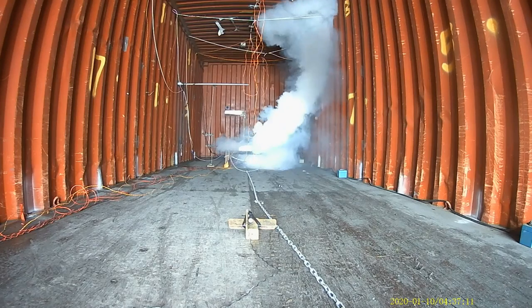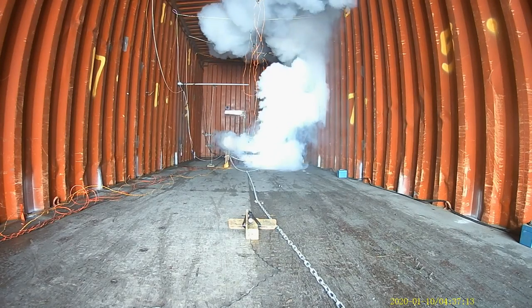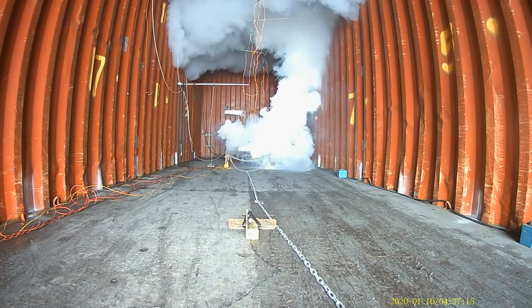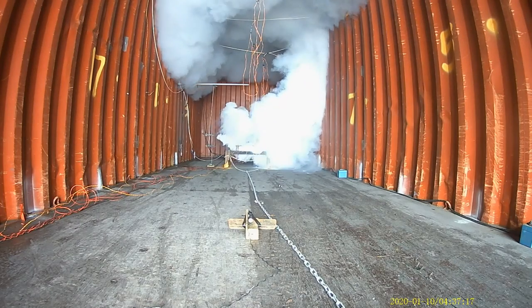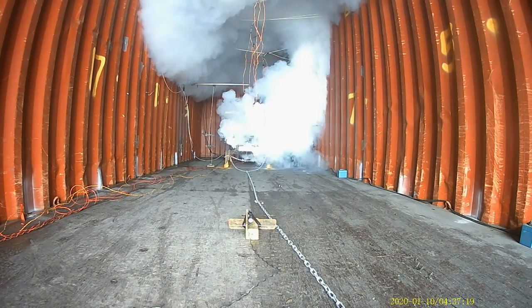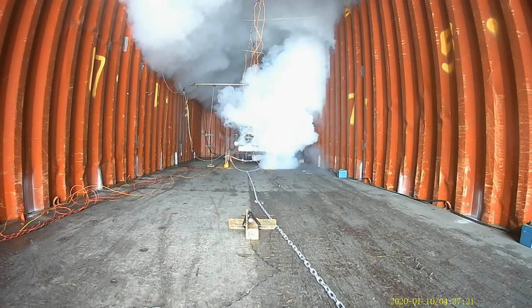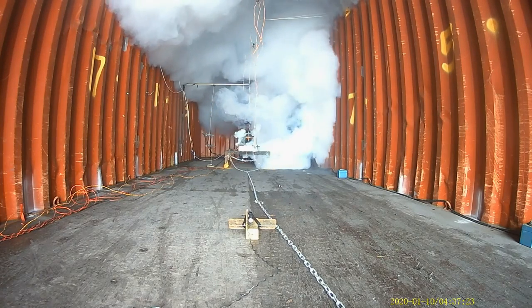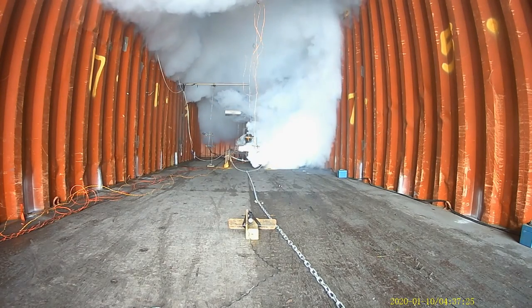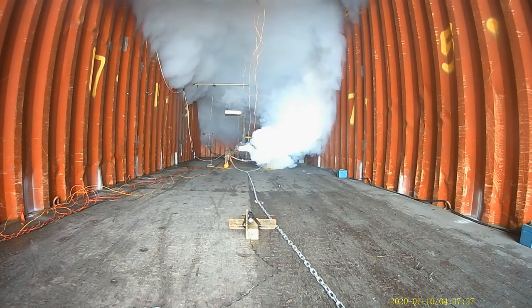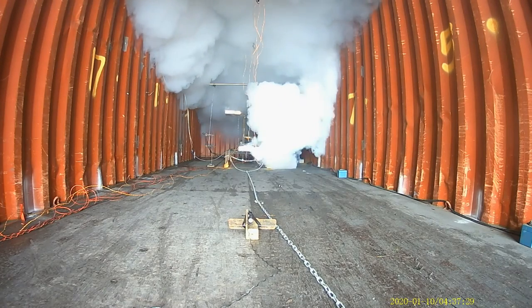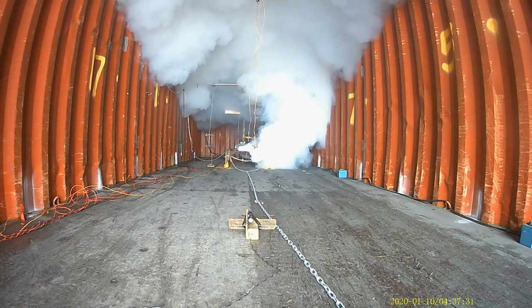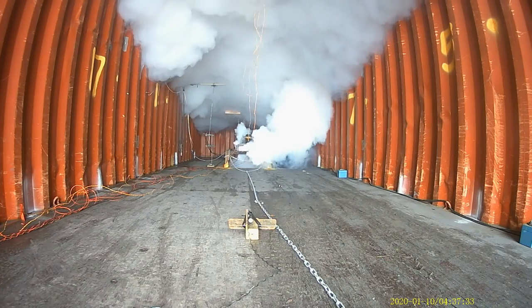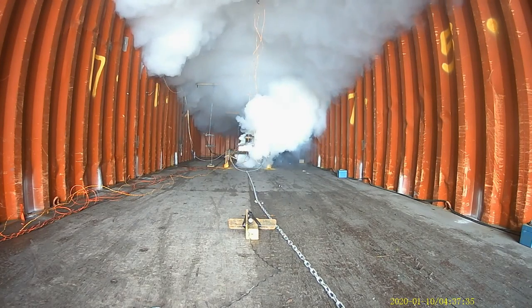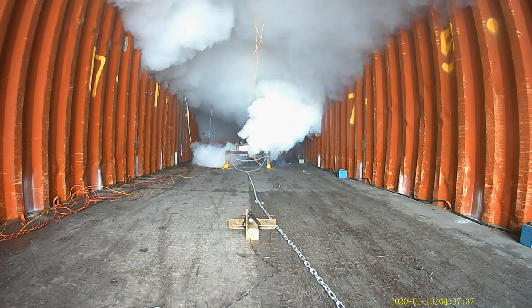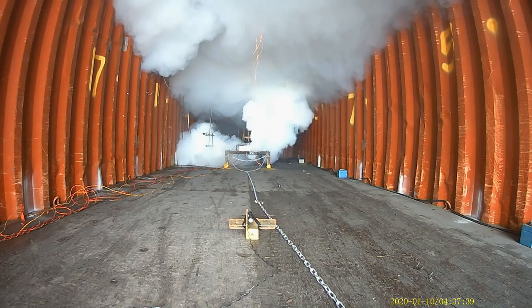What happened there was the ejection of heavy metal particles, and now we're getting the white vapor cloud. We're not sure how much of this vapor cloud we get, but estimates are around 1,000 litres per kilowatt hour. Notice it's lighter than air, it's buoyant, filling the container from the roof downwards. We were trying to ignite this vapor cloud, but it turns out we were below the lower explosion limit.